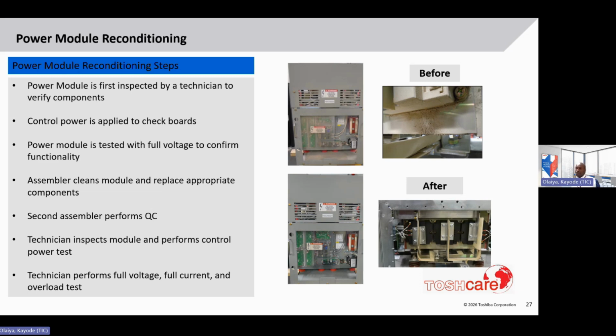In some cases, like the example shown here, the module might not be in the best condition to put into the test stand. And so some preliminary work might be done to it, such as light cleaning and making sure all the connections are properly connected. Once the module has passed that initial test, then an assembler will clean the module, which is a big part of the reconditioning program, as we've gotten to see, is that foreign components are a danger to proper operation. And so the assembler will actually disassemble the module, clean, especially the heatsink, which is on its own a process to clean, and then replace the components, which I'll go into a little more detail in the last slide.